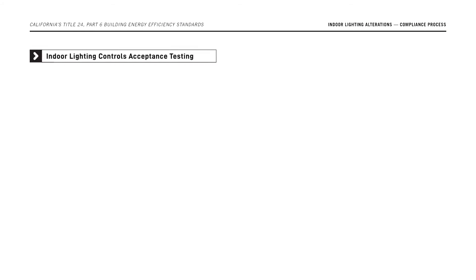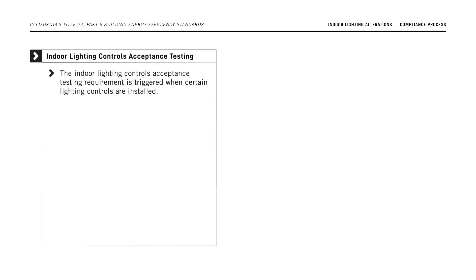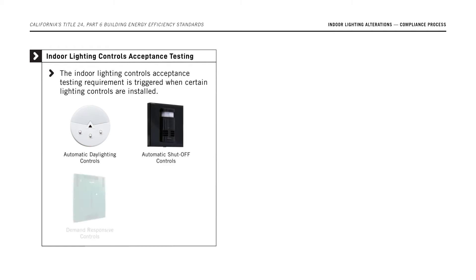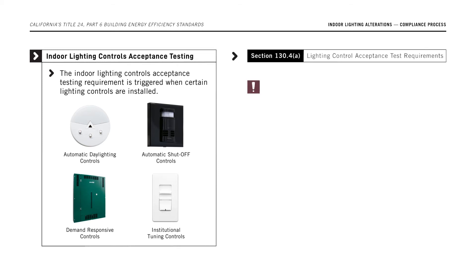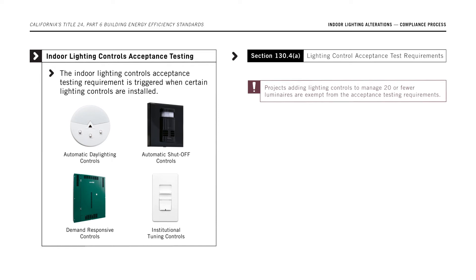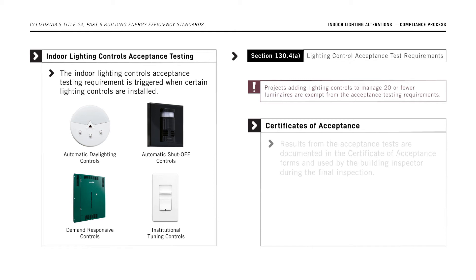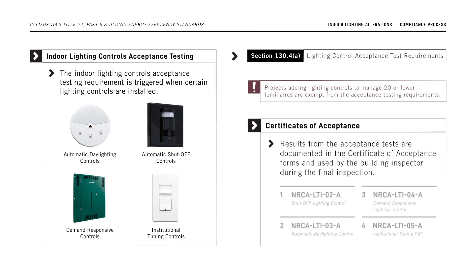The indoor lighting controls acceptance testing requirement is triggered when certain lighting controls are installed. This includes automatic daylighting controls, automatic shutoff controls, demand responsive controls, and institutional tuning controls. These indoor lighting controls must comply with the acceptance testing requirements in Section 130.4. When a project adds lighting controls to manage 20 or fewer luminaires, it is exempt from the acceptance testing requirements. Results from the acceptance tests are documented in the Certificate of Acceptance forms and used by the building inspector during the final inspection.